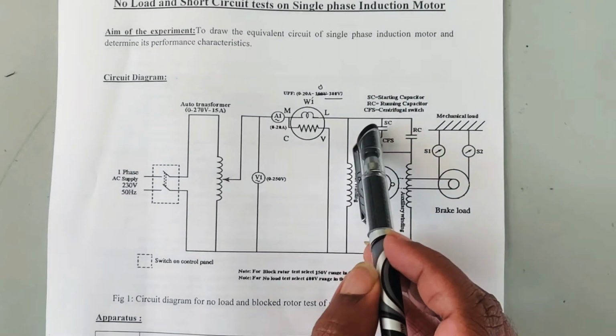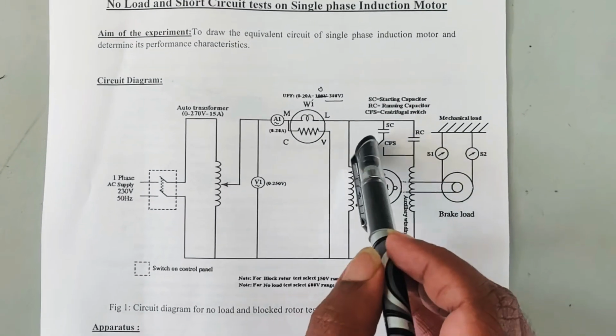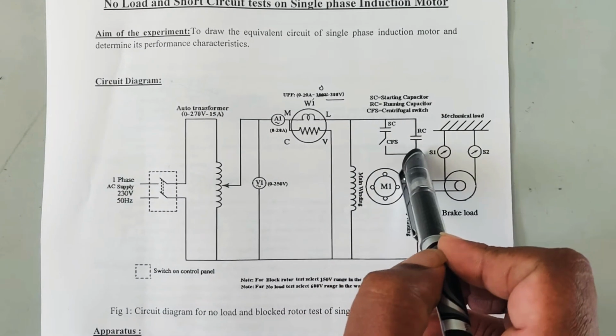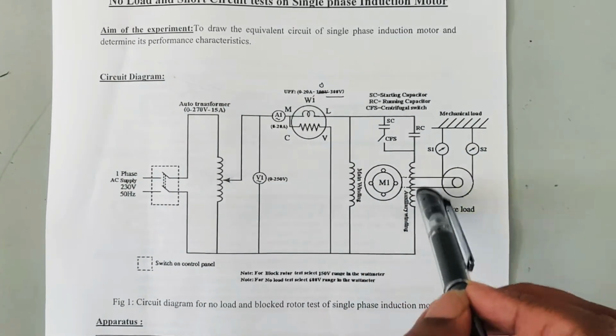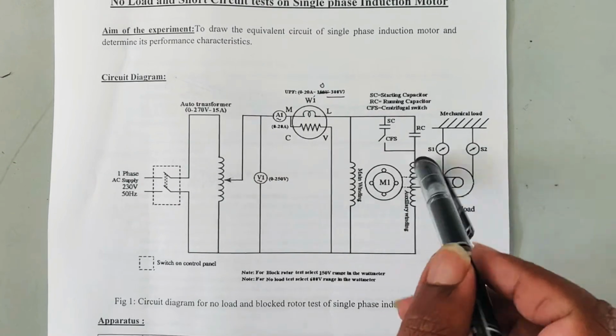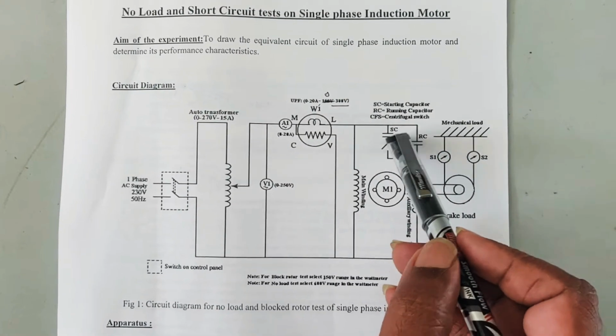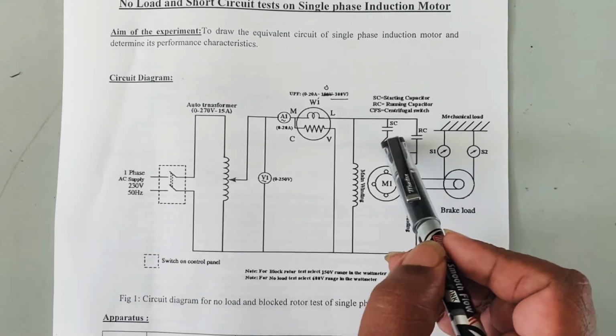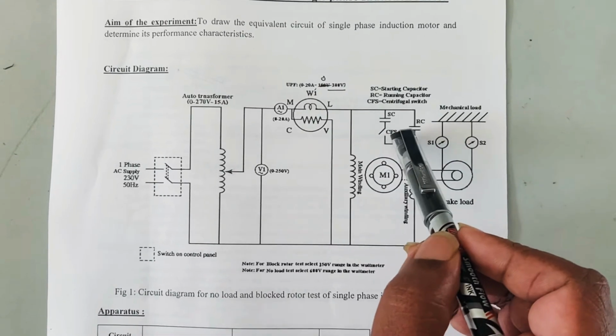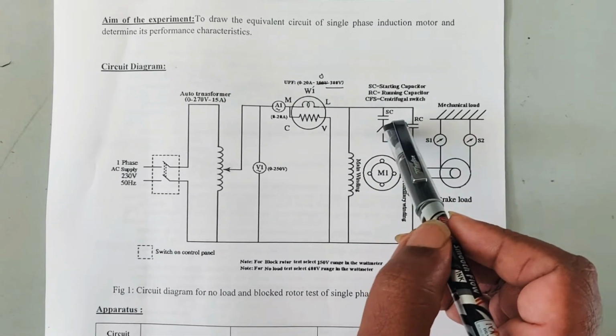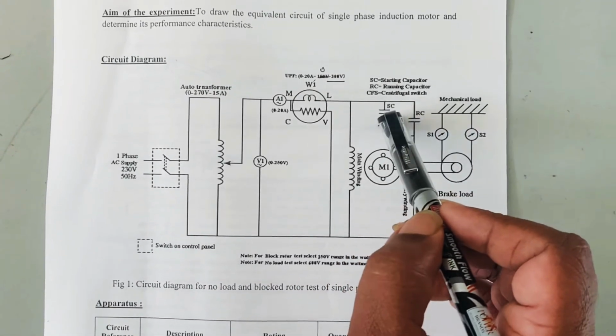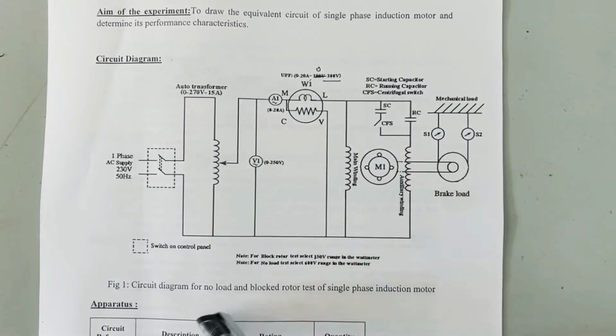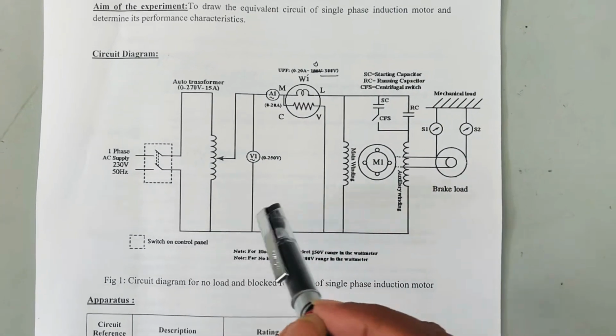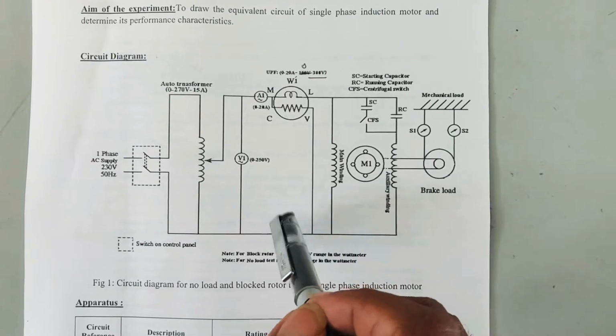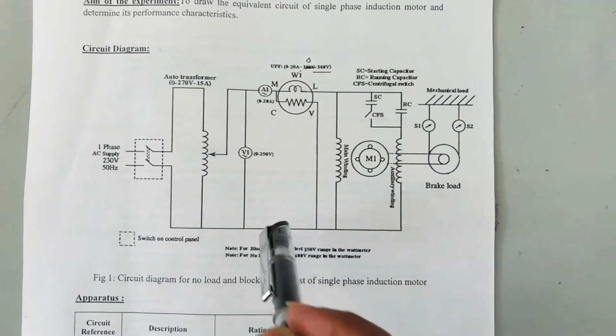So here you can observe SC and RC, two capacitors. One is the starting capacitor and one is the running capacitor. The running capacitor is always connected with the auxiliary winding. The centrifugal switch will operate only during starting. Once the motor starts, because of the centrifugal force it will open and then the starting capacitor gets disconnected. So let us see how to conduct the no load and then blocked rotor test on this. So firstly we shall go with the connection.